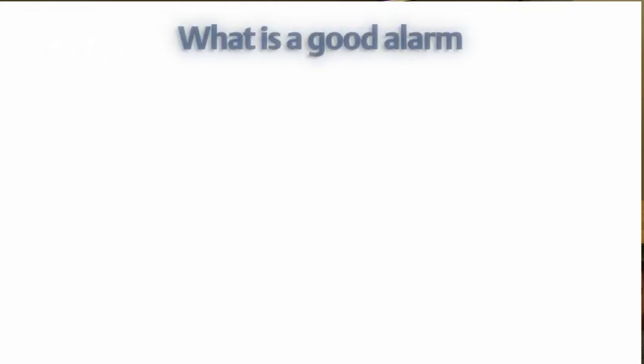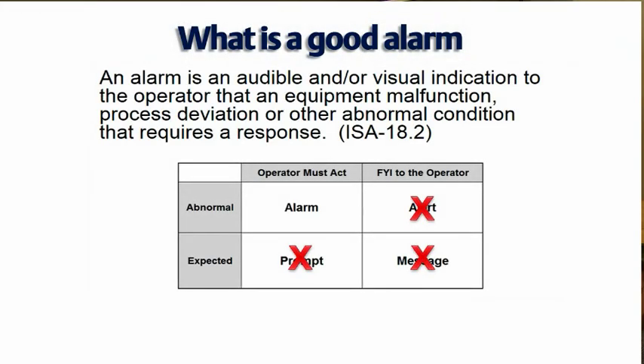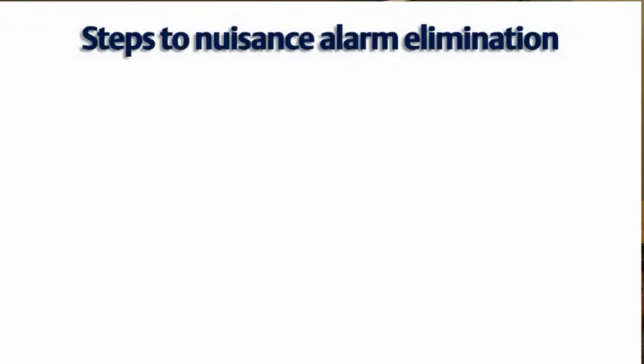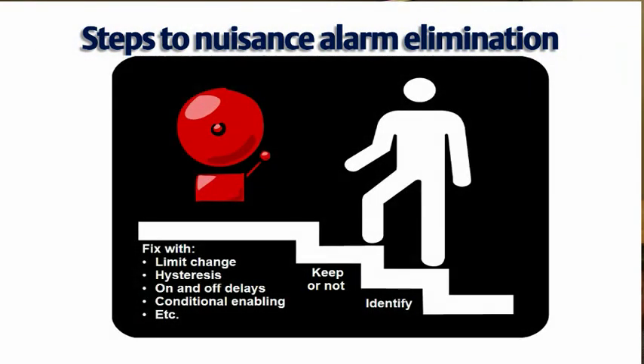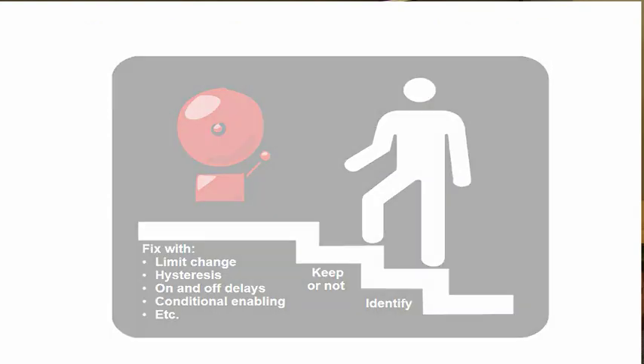The ISA 18.2 standard also defines what constitutes a good alarm. Basically a good alarm is one that indicates a true abnormal condition that requires an operator response. Unfortunately, many alarms do not fit that definition and so we have a lot of nuisance alarms that we need to address. The key to nuisance alarms is first to identify them, which Delta V Analyze will help with, and then to make the decision whether the alarm should be kept or eliminated, and then some settings to fine tune that alarm so it behaves well.